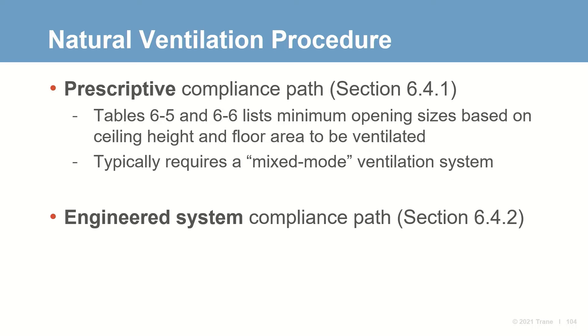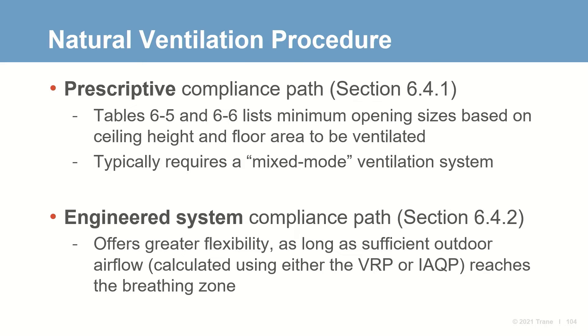Using the prescriptive path typically requires a mixed-mode ventilation system. On the other hand, the engineered systems compliance path offers greater flexibility to design the natural ventilation system, as long as you show that sufficient outdoor airflow reaches the breathing zone.